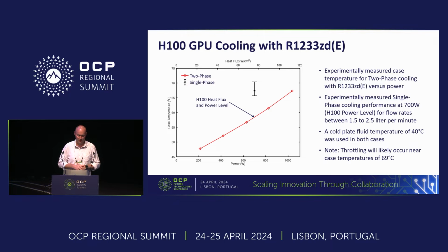As a point of reference, we put in some information for a single-phase water cold plate tested over a range of flow rates at 700 watts. That's what you see in that error bar, showing the change in performance from 1.5 liters per minute of flow down to 2.5 liters per minute of flow. In their case, it ran a couple degrees hotter, maybe much closer to the junction temperature.